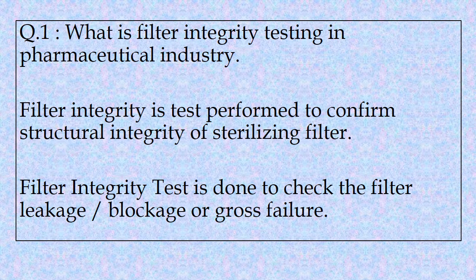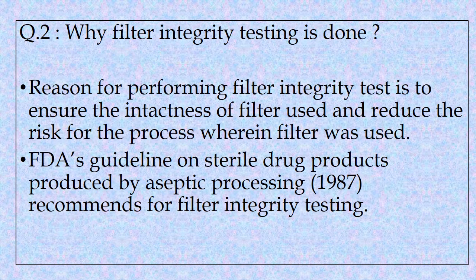Question 1: What is filter integrity testing in the pharmaceutical industry? Filter integrity test is performed to confirm the structural integrity of a sterilizing filter. Filter integrity test is done to check filter leakage, blockage, or gross failure.